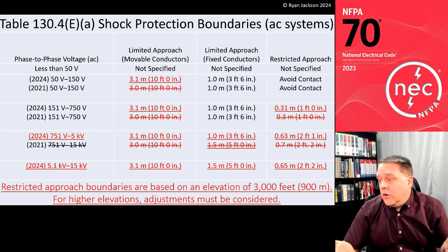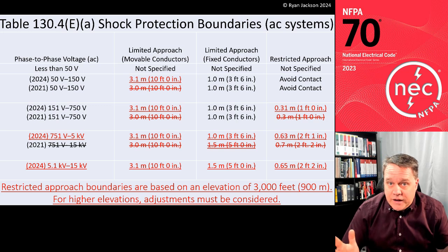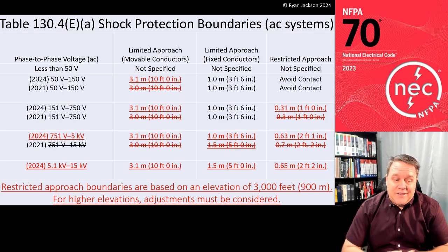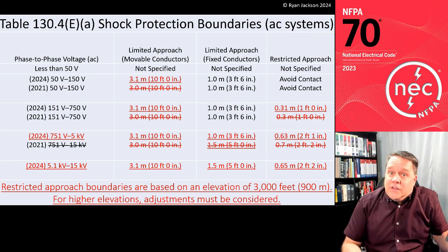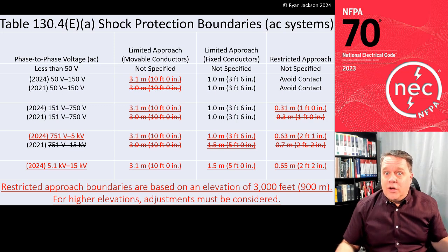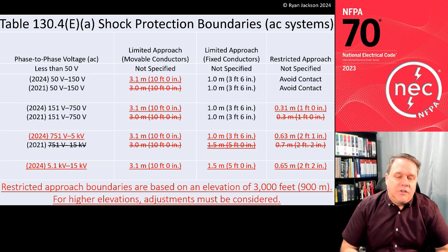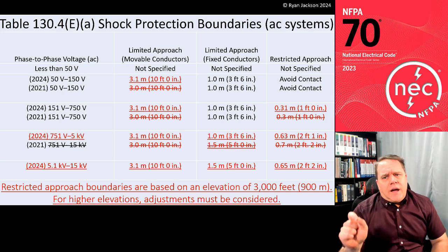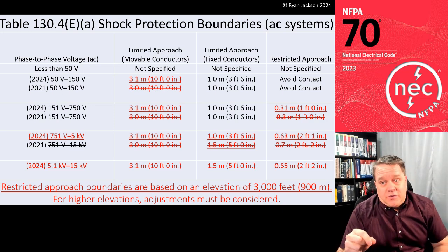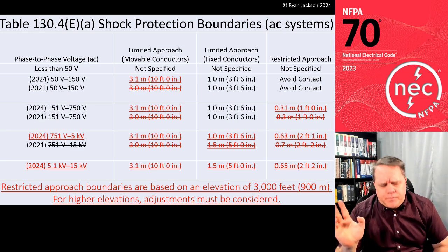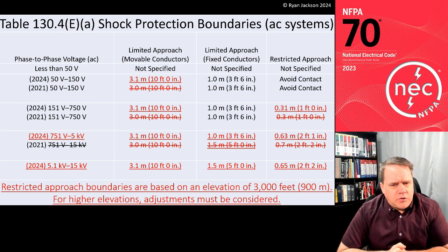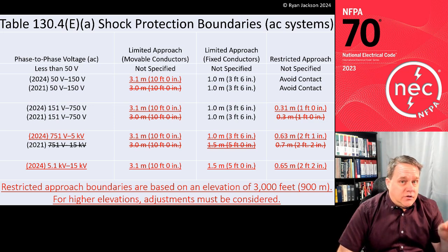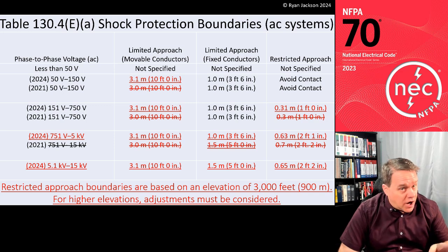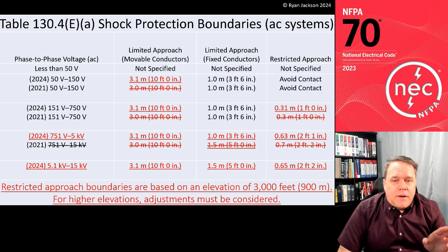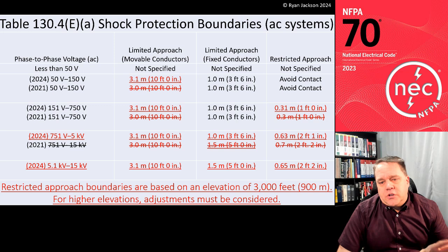So, yeah, you can roll your eyes and say how dumb this is, and I get it. But the fact of the matter is, this standard needs to at least satisfy OSHA, right? I think we all agree with that. So we had to change the table. They also added a note here to the table, and this actually correlates with OSHA requirements. That says restricted approach boundaries. Now, that's not having to do with arc flash, right? That's shock. So restricted approach boundaries are based on an elevation of 3,000 feet or 900 meters.